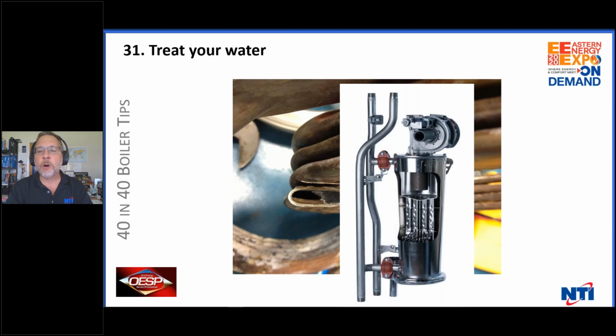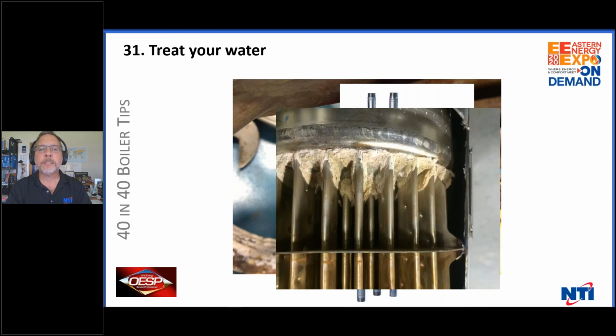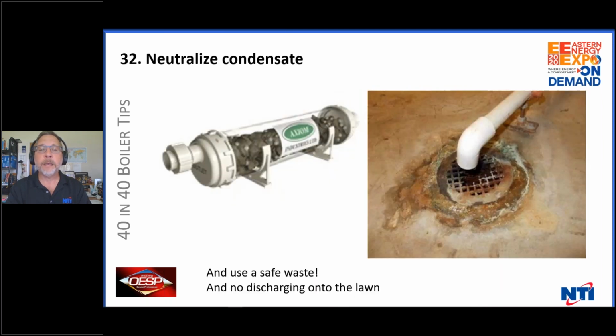But it also happens on water tube or fire tube boilers. Fire tube boilers, everybody loves them. Larger mass, you know, they're less cleaning, lower head, phenomenal. We carry both. We make both. They're both lovely. They both work great when applied correctly, but they fail too. This is a system that they left the water fill on with constant water coming in, constant fresh water coming in with calcium built up on the tube sheet on the top where the fire is, created hot and cold spots and cracked the tube sheet. This also happens with iron. The iron oxide or magnetite will do the exact same thing.